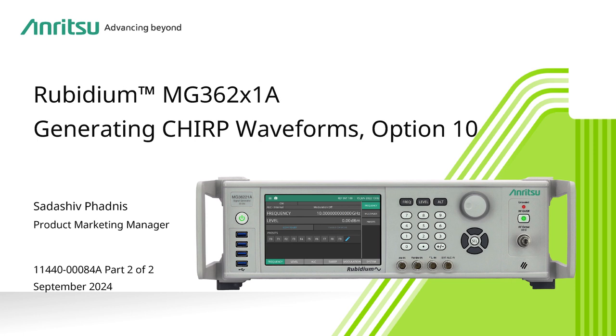It is also possible to enable a combination of modulation schemes simultaneously. This video will show how to create a CHIRP using user-defined modulation option by enabling internal FM and pulse modulations simultaneously.